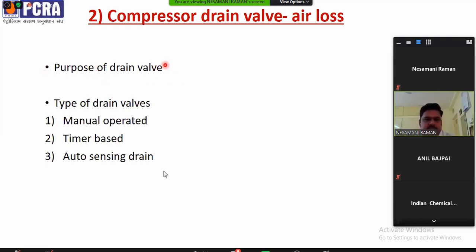The purpose of the drain valve is removing the excess moisture in the compressed air, so that the moisture is not carried away with the air, which would corrode the pipelines as well as the instruments. So that is the purpose of drain valves. But actually what happens, we'll see. There are types of drain valves. One is a manually operated drain valve, meaning the shift person will operate it every shift or once in a day.